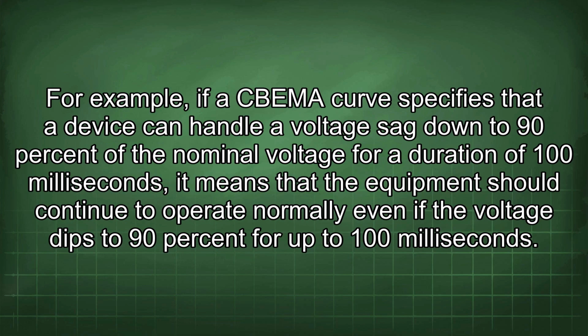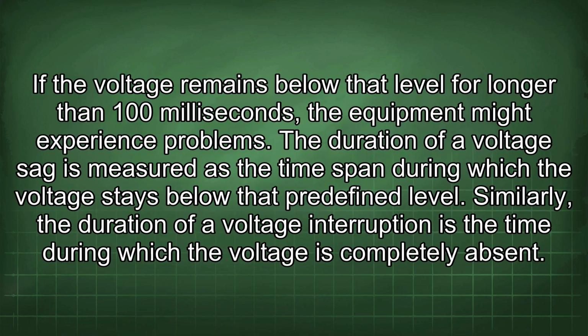For example, if a CBEMA curve specifies that a device can handle a voltage sag down to 90% of the nominal voltage for a duration of 100 milliseconds, it means that the equipment should continue to operate normally even if the voltage dips to 90% for up to 100 milliseconds. If the voltage remains below that level for longer than 100 milliseconds, the equipment might experience problems. The duration of a voltage sag is measured as the time span during which the voltage stays below that predefined level. Similarly, the duration of a voltage interruption is the time during which the voltage is completely absent.